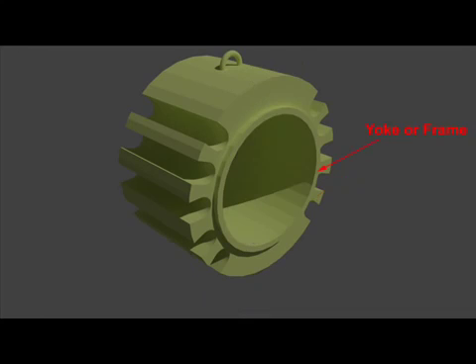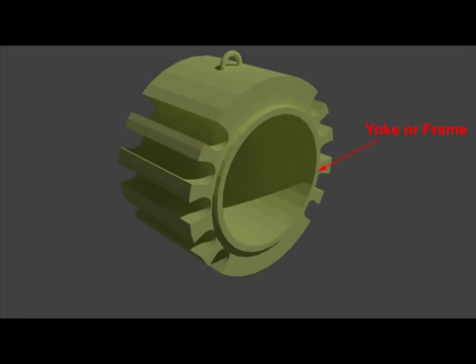The yoke is generally of cylindrical shape. The yoke acts as a cover frame of the machine and carries the magnetic flux produced by the poles. Since the field is stationary, there is no need to use laminated yoke for normal machines. In small machines, cast iron yokes are used because of cheapness, but the yoke of a large machine is made of fabricated steel due to its high permeability.